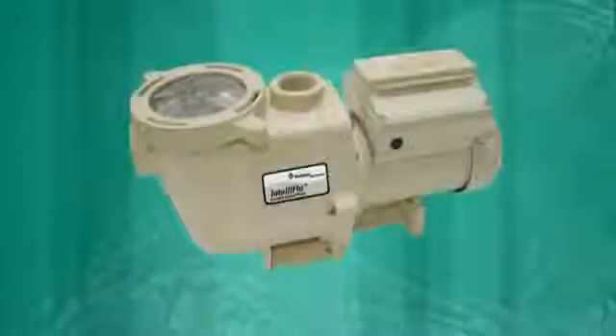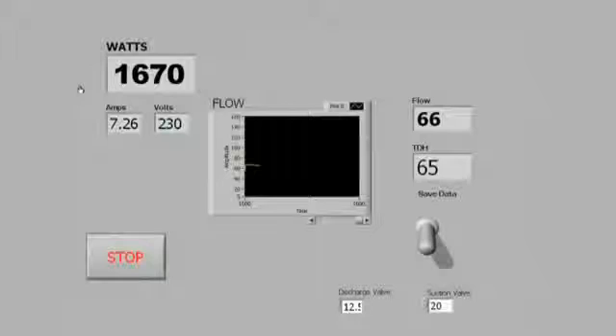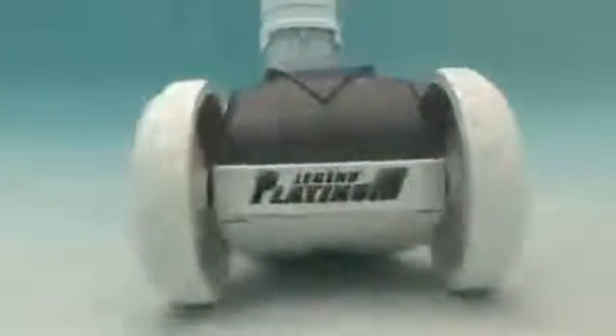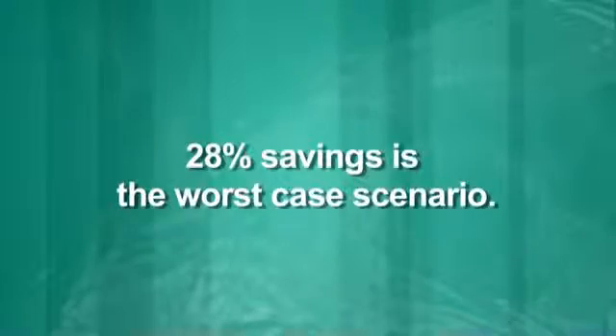Finally, let's go to the opposite extreme and compare an IntelliFlo with a less powerful one-horsepower pump running at a speed of 3,600 RPMs. Here, the watt usage decreases from 1,670 to 1,196, which is a 28% energy savings. But also remember, you have the ability to reduce the speed of the IntelliFlo and further reduce power requirements for different routines throughout the day, week, or season. Therefore, a 28% savings is actually the worst-case scenario — because the more you customize IntelliFlo's performance for each pool function, the greater the savings potential.